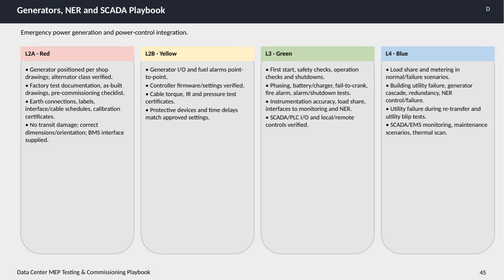Finally, level 4, shown in blue, centers on load sharing and metering during both normal and failure scenarios. We simulate building utility failures, generator cascade operations, system redundancy, and NER control and failure modes. Utility failures during retransfer and utility blip tests are also tested.